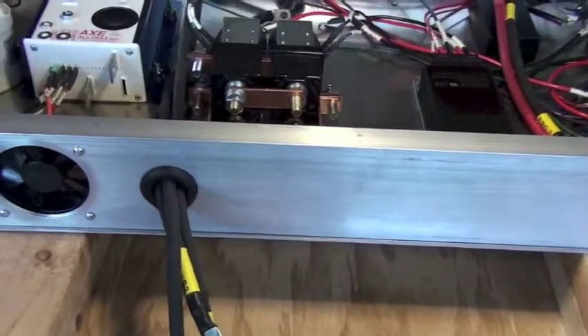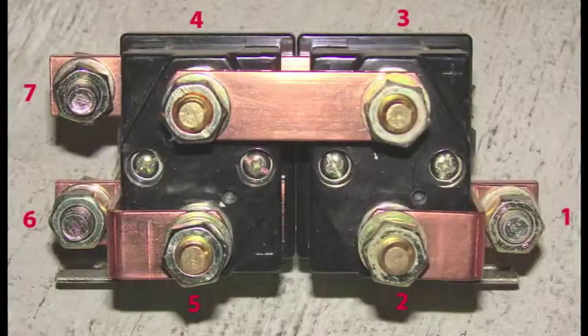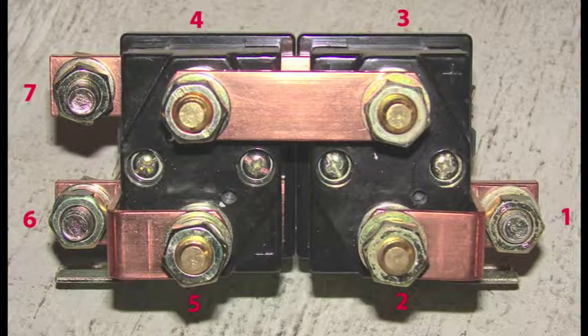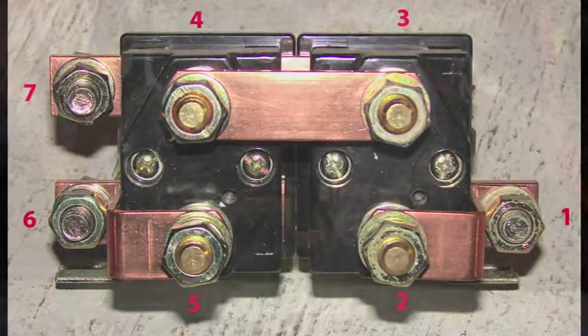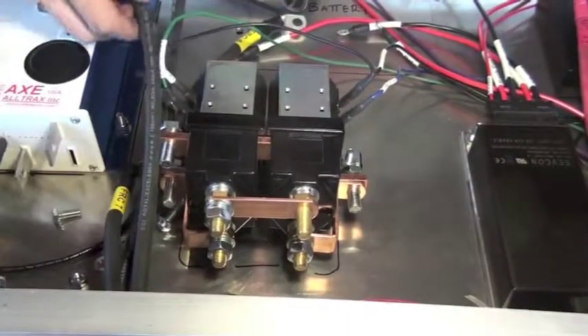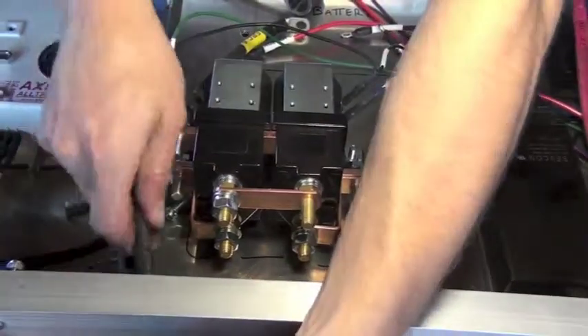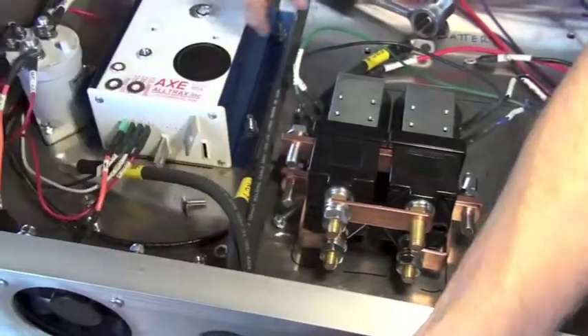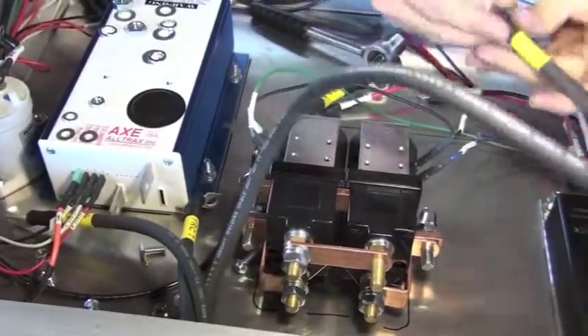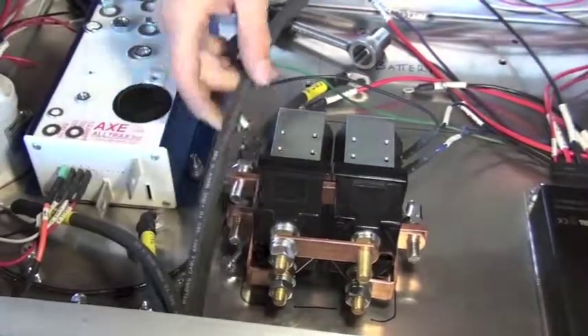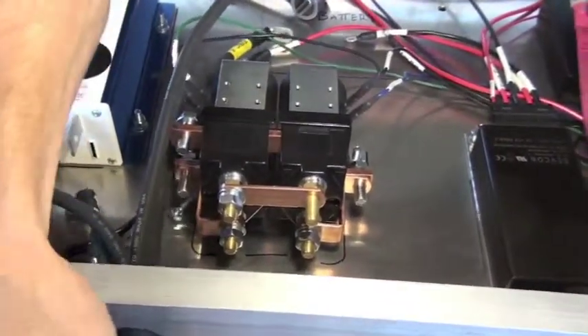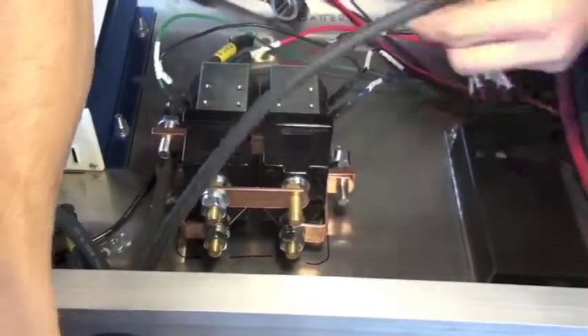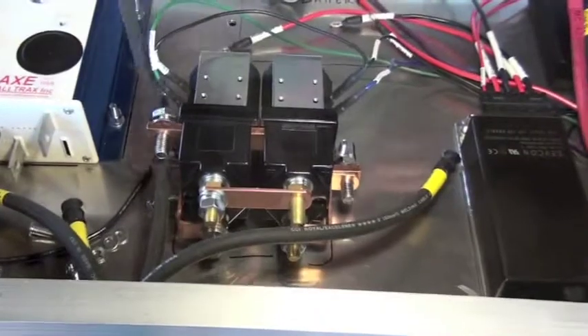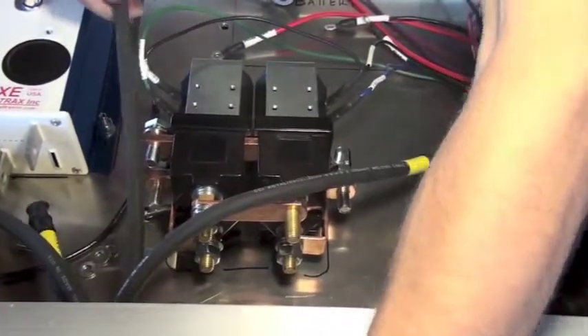So let's take a look at our forward and reverse contactor setup. And remember that the numbered terminals in these contactors flow according to the way that the copper connects them. So we have 1 connected to 2, 3 to 4, 5 to 6, and then 7 by itself. You just want to leave your cable ends as close to their termination points as possible as you're sending them through the opening in the box. So here we can see this one goes to the controller. This cable that still needs some work to go through goes to contactor point number 1. So we'll just pull that through to match it up. You just got to get it roughly close to where it's going to connect. And do this with all of the termination points. It'll make the assembly much easier.